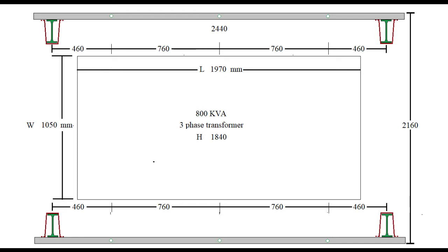Now these poles are ready to receive C girders fitted from outside of each pair of poles. A plan view of such a substation is shown on screen. The substation consists of 4 poles, and 2 of them are used to receive the incoming feeder. The girders at the top of these 2 poles are fitted using 2 clamps that are tightened using nuts, bolts and washers. The 3 holes that we see on these girders carry another set of bolts, nuts and washers to couple string insulators suitable for 11 kV voltage.